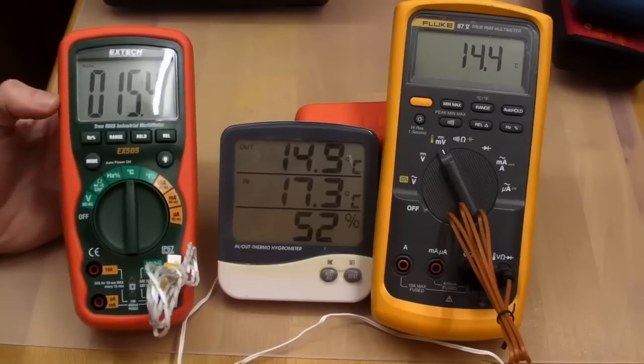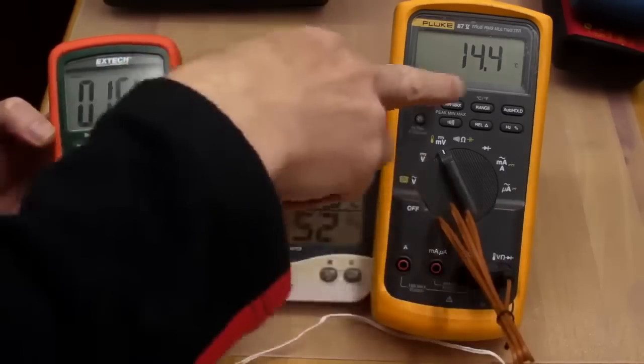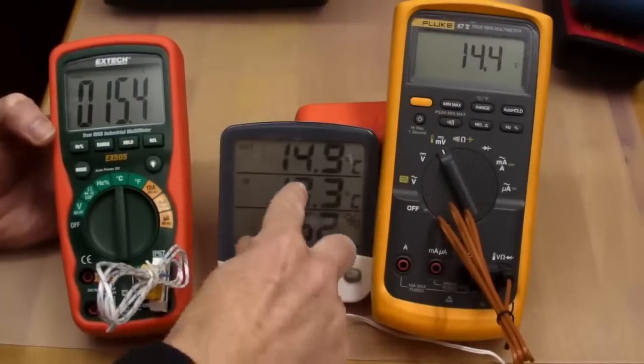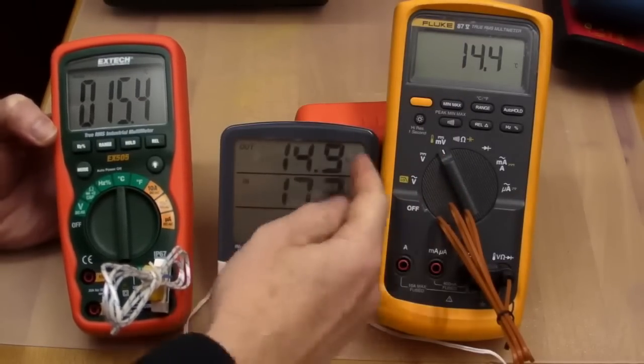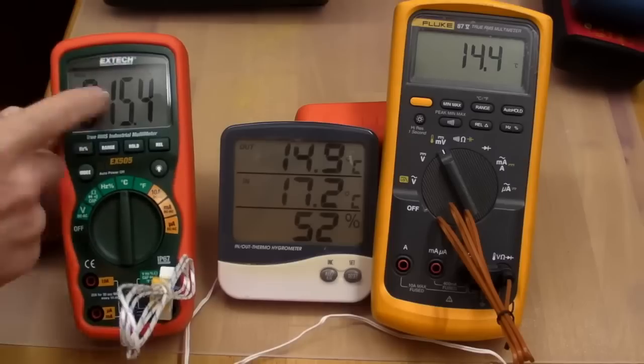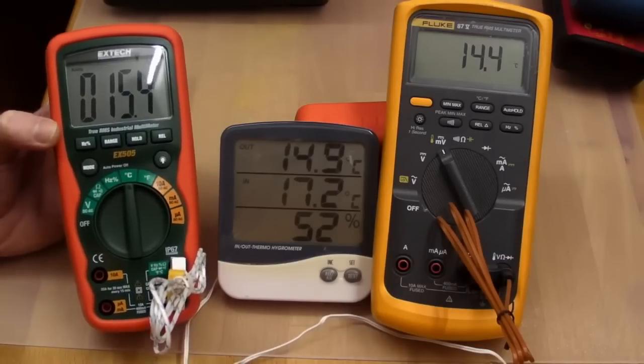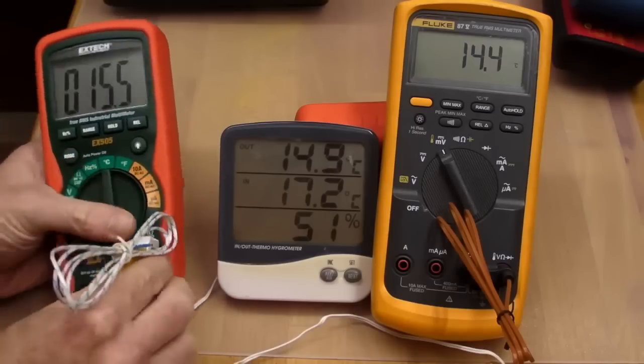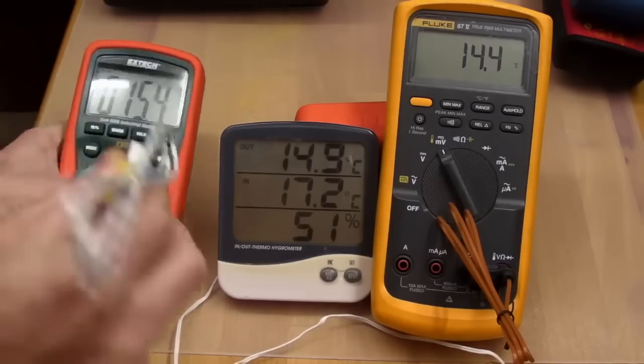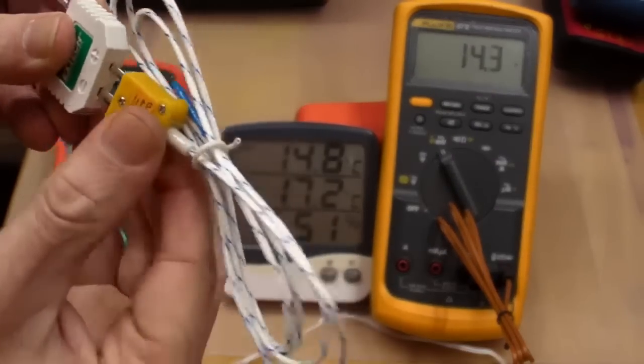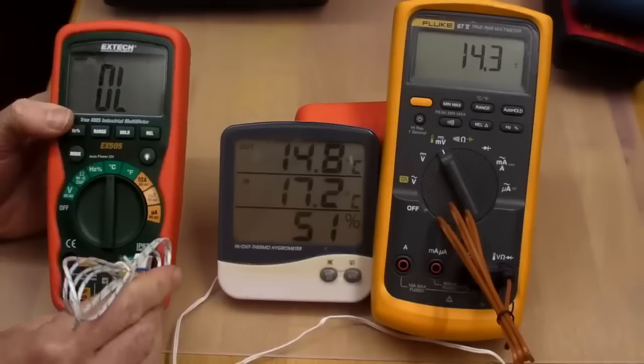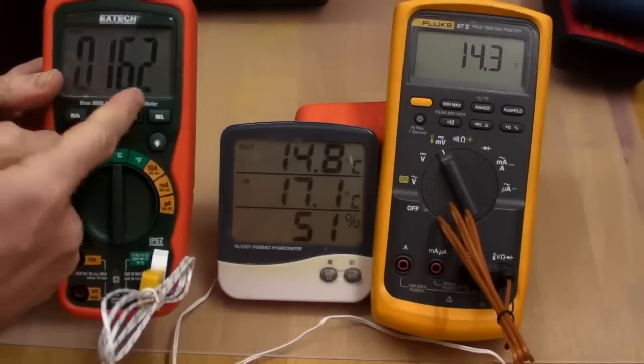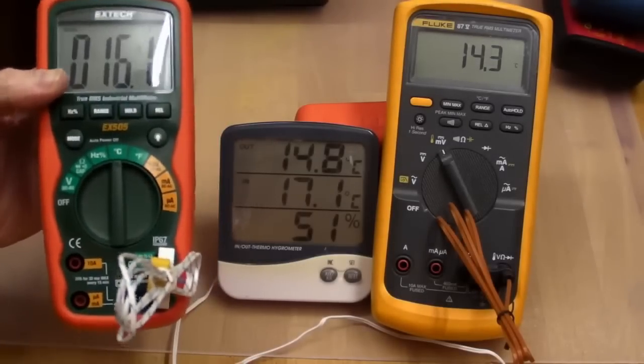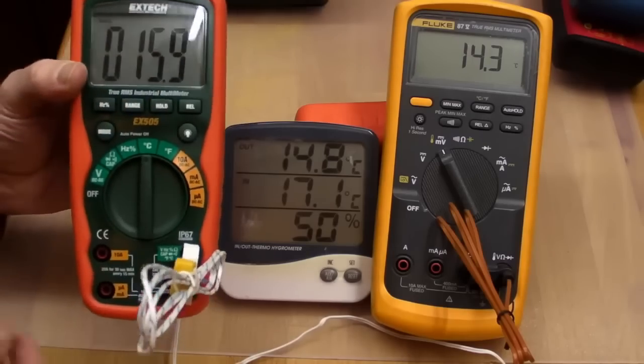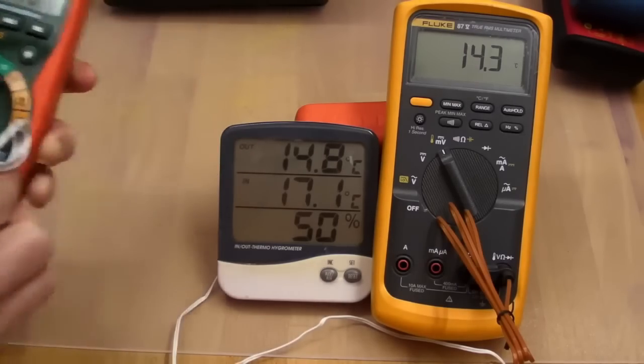Let's just do a quick temperature measurement. I've got the Fluke reference one here, 14.4 degrees Celsius. I've got another el cheapo thermometer here, 14.9, and the Extech's doing 15.4, which isn't too bad at all. It comes with this little thermocouple adapter, reasonable, but it just accepts a standard K-type, so it's not too bad. The good thing about the Extech is it does give you 0.1 degree resolution, which is excellent. Not all meters will actually do that.